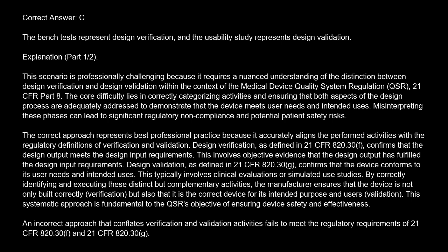By correctly identifying and executing these distinct but complementary activities, the manufacturer ensures that the device is not only built correctly (verification), but also that it is the correct device for its intended purpose and users (validation). This systematic approach is fundamental to the QSR's objective of ensuring device safety and effectiveness.